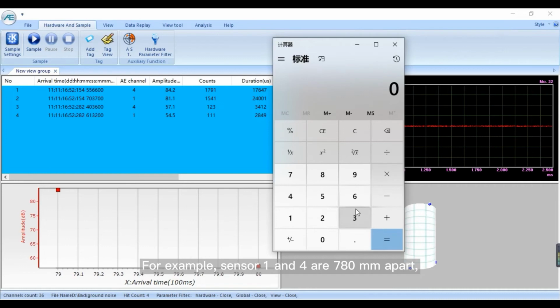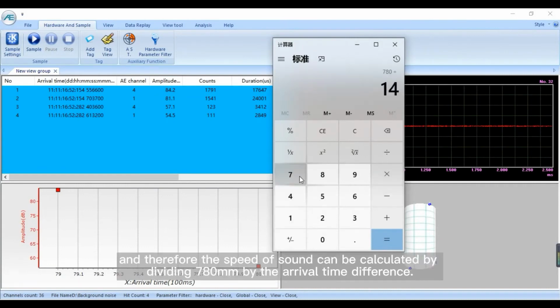For example, sensor 1 and 4 are 780 millimeters apart. We can get the arrival time difference, and therefore the speed of sound can be calculated by dividing 780 millimeters by the arrival time difference.